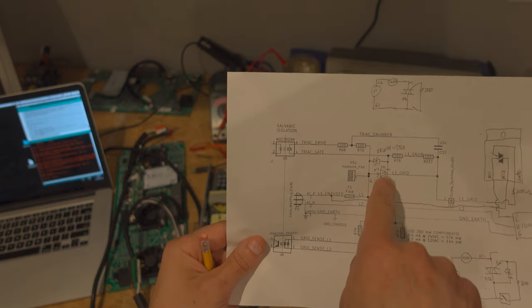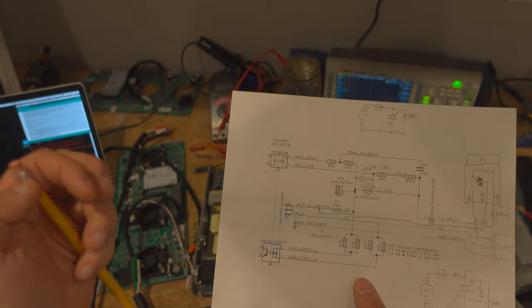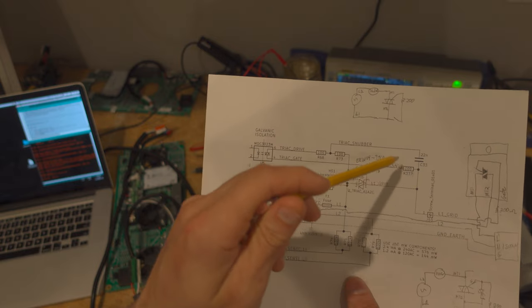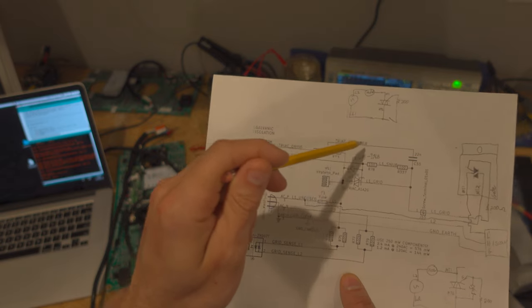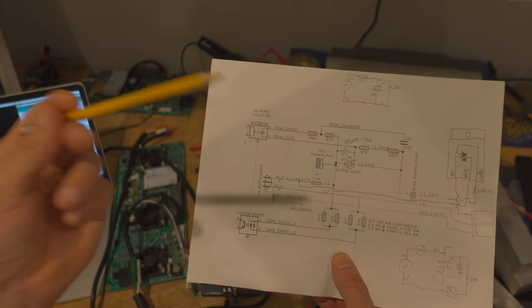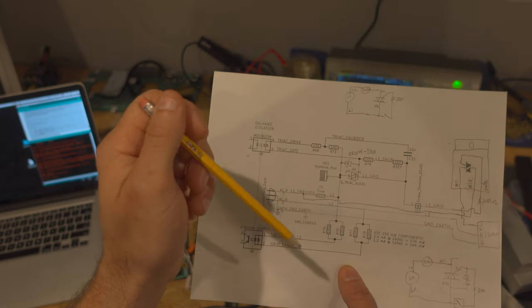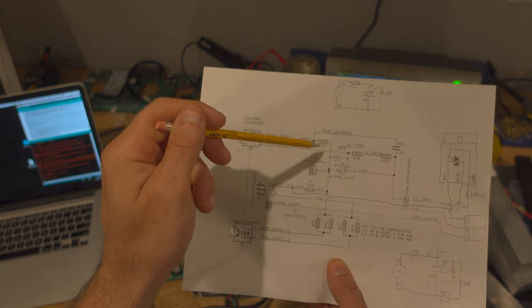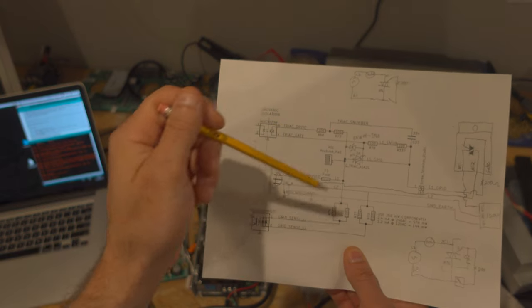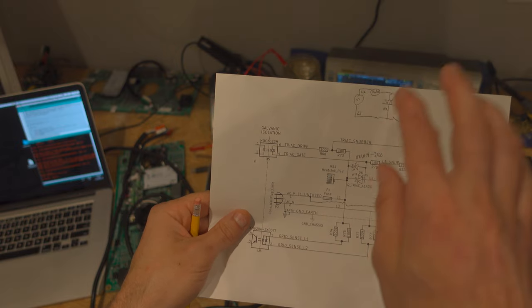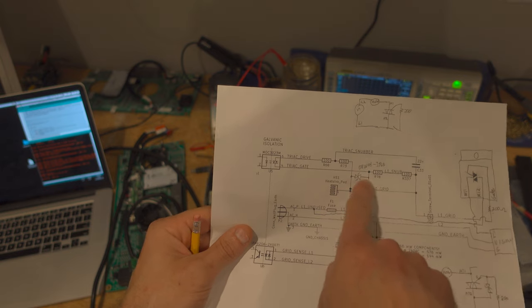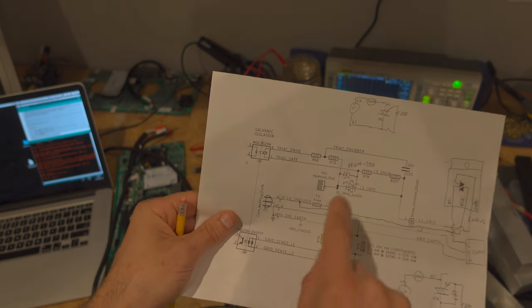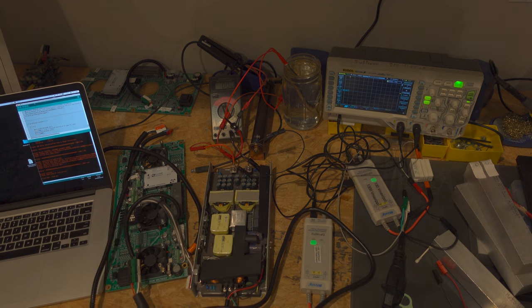What you do is you have a snubber here and this snubber basically increases that voltage range. The high frequency components, say when a tree falls on your primary line and blows stuff in your house out, you basically have an alternate path through this 100 ohm resistor coming through this 22 nanofarad cap. This is going to eat up what would otherwise be an overvoltage event. This isn't sinking power like if you had a TVS diode or a metal oxide varistor. We're not actually sinking as joule heat here. All this is doing is taking high frequency components and making the line one side basically the same voltage. Because this whole thing is floating, if you have a million volts there and a million and 100 volts there, this is still fine because we don't have 800 volts across the MT1 or MT2 terminals.